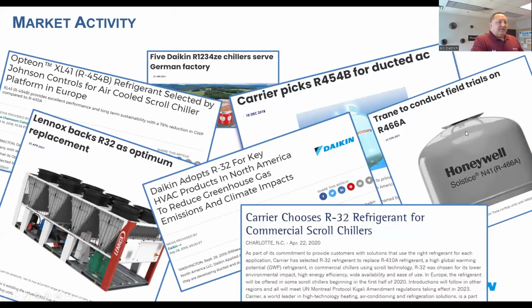We look at the market activity, like I said, we've got Carrier, for example, choosing R32 in scroll chillers, but they picked R454B for their ducted, more unitary light commercial AC. Trane is doing trials on the 466A. Daikin adopts R32. We see 1234ZE in factories. JCI is using 454B in Europe. Lennox specs R32. So we're going to go from a market, especially in the 410 market, where everybody's using the same thing, to where there could be at least probably two, the R32 and the 454B, becoming pretty common in the market. Time will tell to see if the 466 gets there.